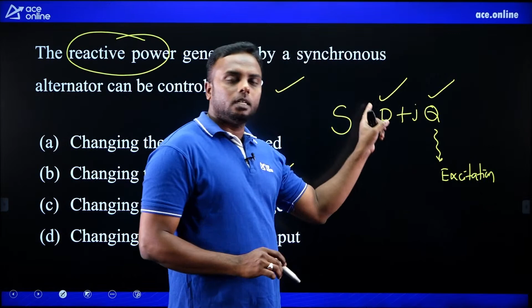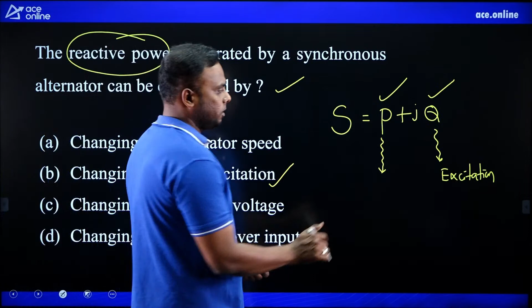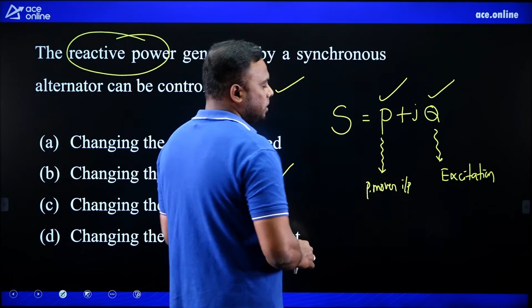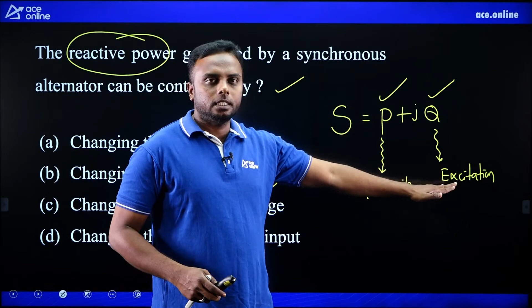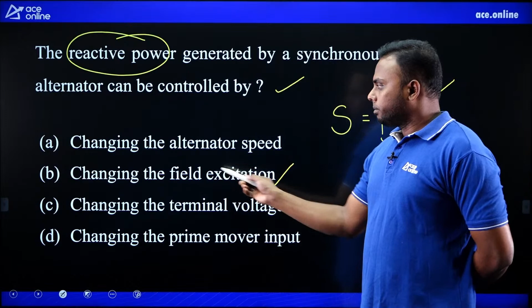Next, if you want to change the active power of an alternator mainly, which one do we have to change? We have to change the prime mover input, or mechanical input. So with variation in prime mover input, the active power of the alternator mainly changes, and with change in excitation, the reactive power mainly changes. So the answer is option B, changing field excitation.